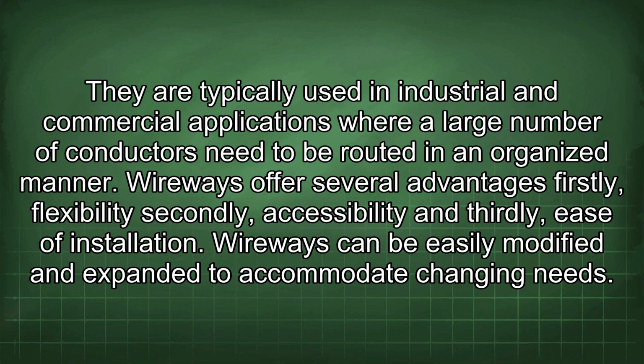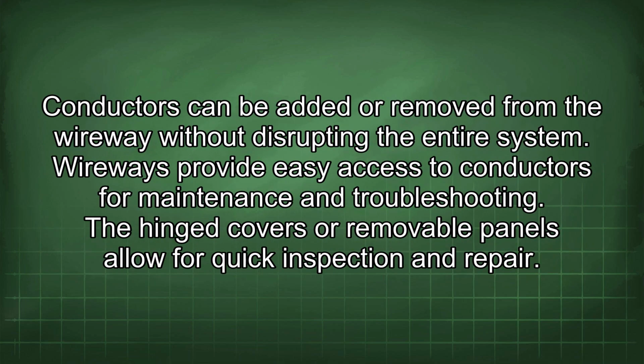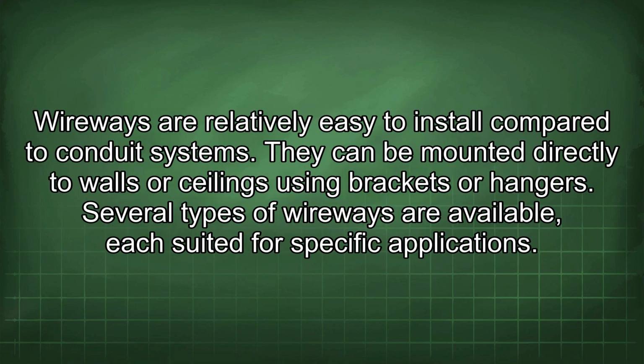Wireways can be easily modified and expanded to accommodate changing needs. Conductors can be added or removed from the wireway without disrupting the entire system. Wireways provide easy access to conductors for maintenance and troubleshooting. The hinged covers or removable panels allow for quick inspection and repair. Wireways are relatively easy to install compared to conduit systems. They can be mounted directly to walls or ceilings using brackets or hangers.